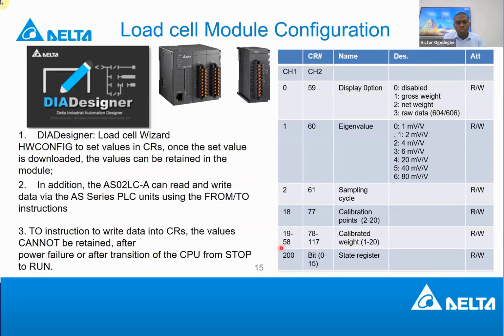And then if we proceed further, you'll see there's also another register, register 200. This register is for both channel 1 and channel 2. What this register does is it's a state register. It gives an indication of what is happening in the module. Normally when there's an error, some bits from bit 0 to bit 15 could turn on, indicating that in this very bit there is an error. And you can reconcile that error to what is happening in the module, because each bit has a meaning. I think I have it later on. You see it, I think, at the end of the presentation.